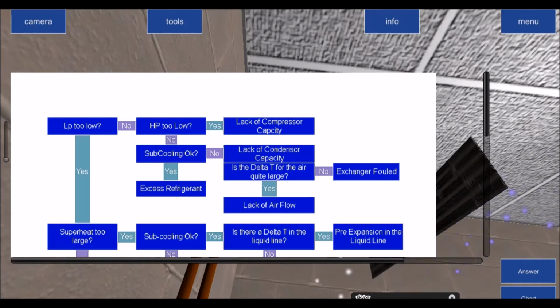So anything from 6 up is higher. So 7 degrees evaporating temperature with an air on of 10 gives me a delta T total of 3. We need a minimum delta T total of 5 and a maximum of 10. In this case, we have a delta T total of 3. That means my evaporating temperature is higher than I would expect it to be with the air on temperature of 10 degrees. So is LP too low? No. LP is not too low. If anything, it's too high. Goes back to, is HP too low?